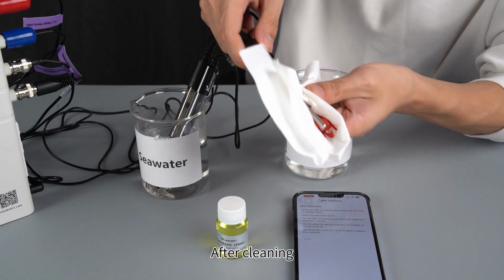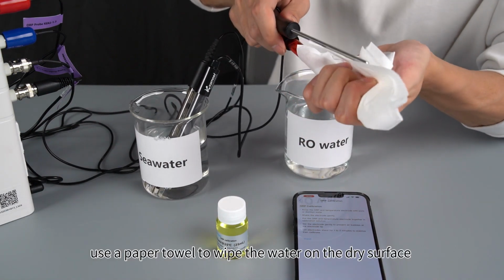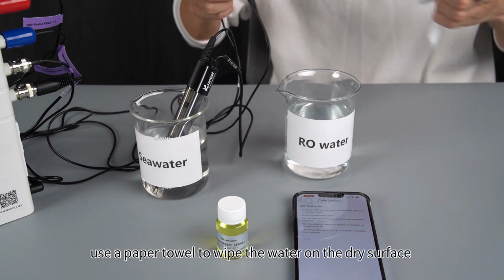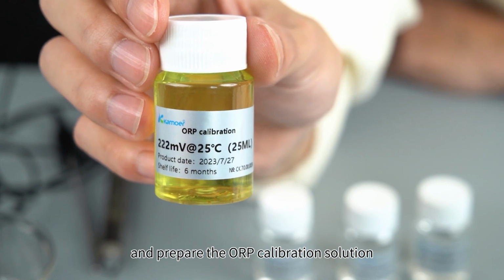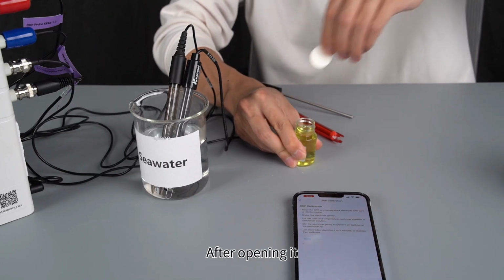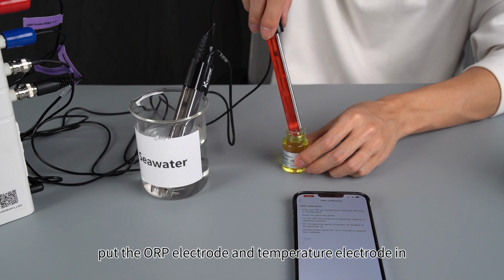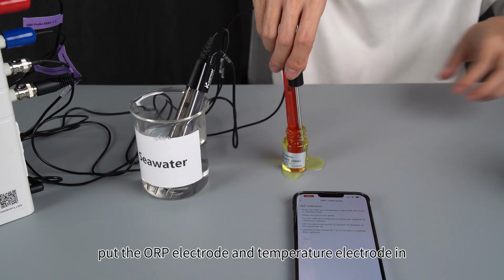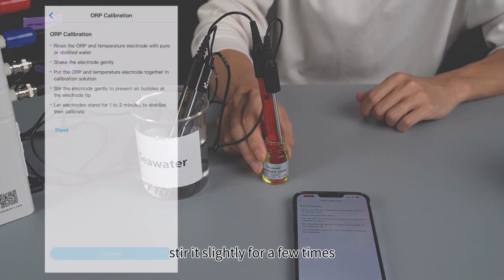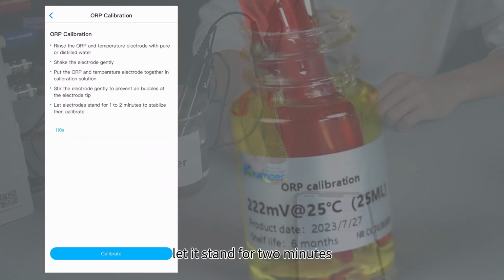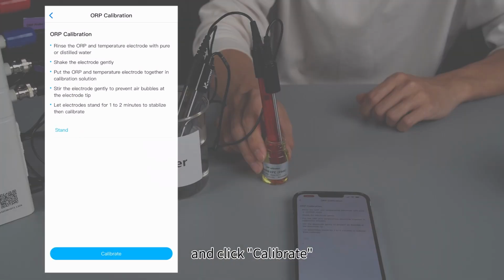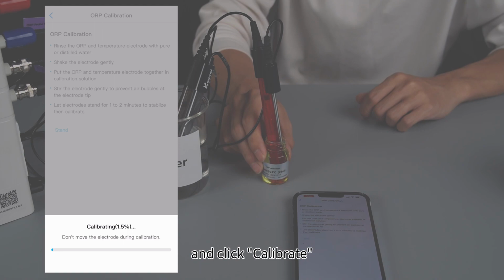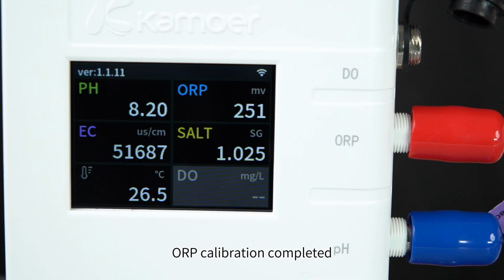After cleaning, use a paper towel to wipe the water on the surface dry and prepare the ORP calibration solution. After opening it, put the ORP electrode and temperature electrode in. Stir it slightly a few times. Click Stand. Let it stand for 2 minutes. And click Calibrate. ORP calibration completed.